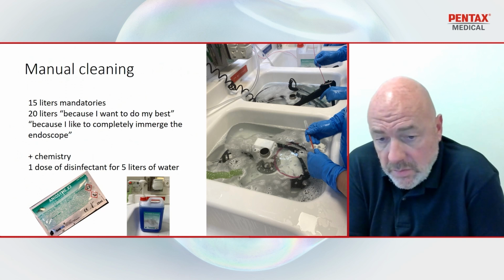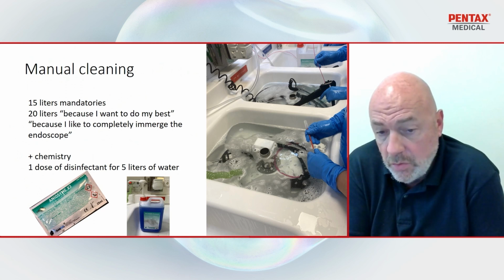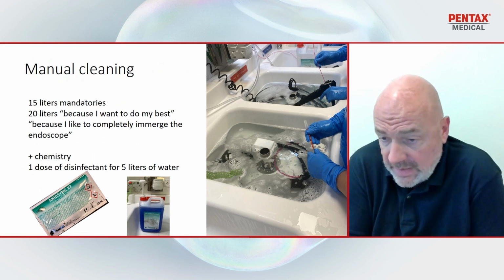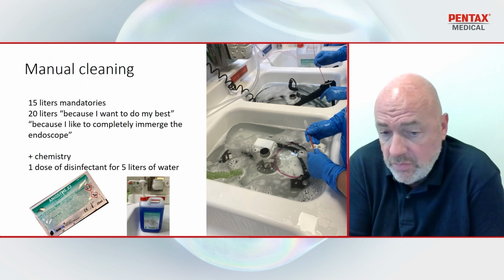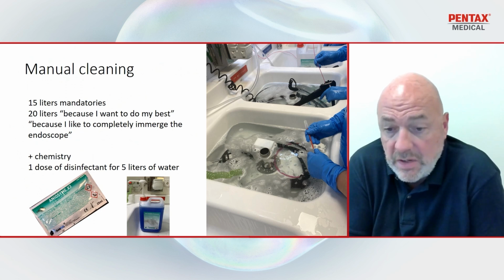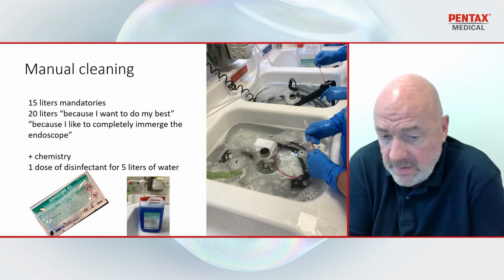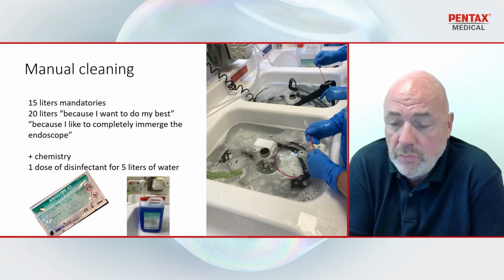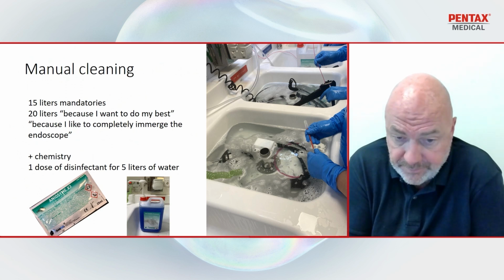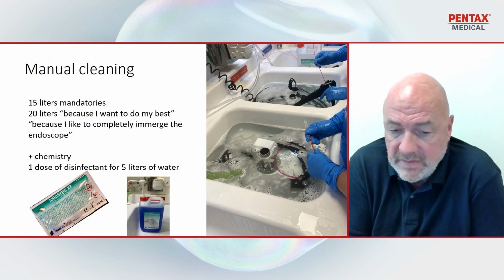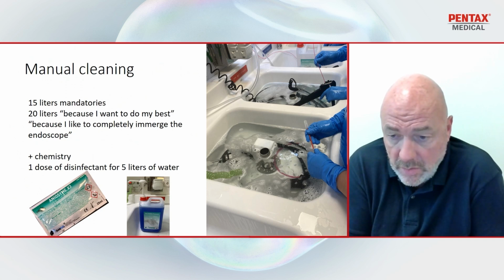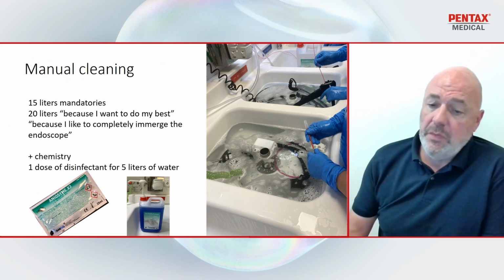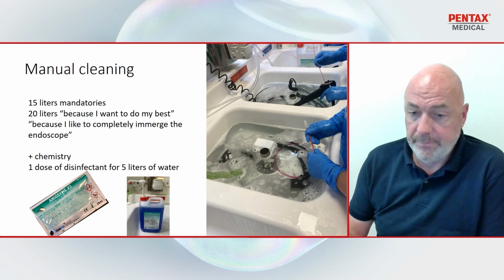If you look at the manual cleaning, you normally need 15 liters, mandatory. But when I look at the staff, they use 20 liters daily, because they want to do their best. They like to completely immerse the endoscope. So 20 liters daily is very big consumption. After the water, you add chemistry, 1 dose of chemistry for 5 liters of water.